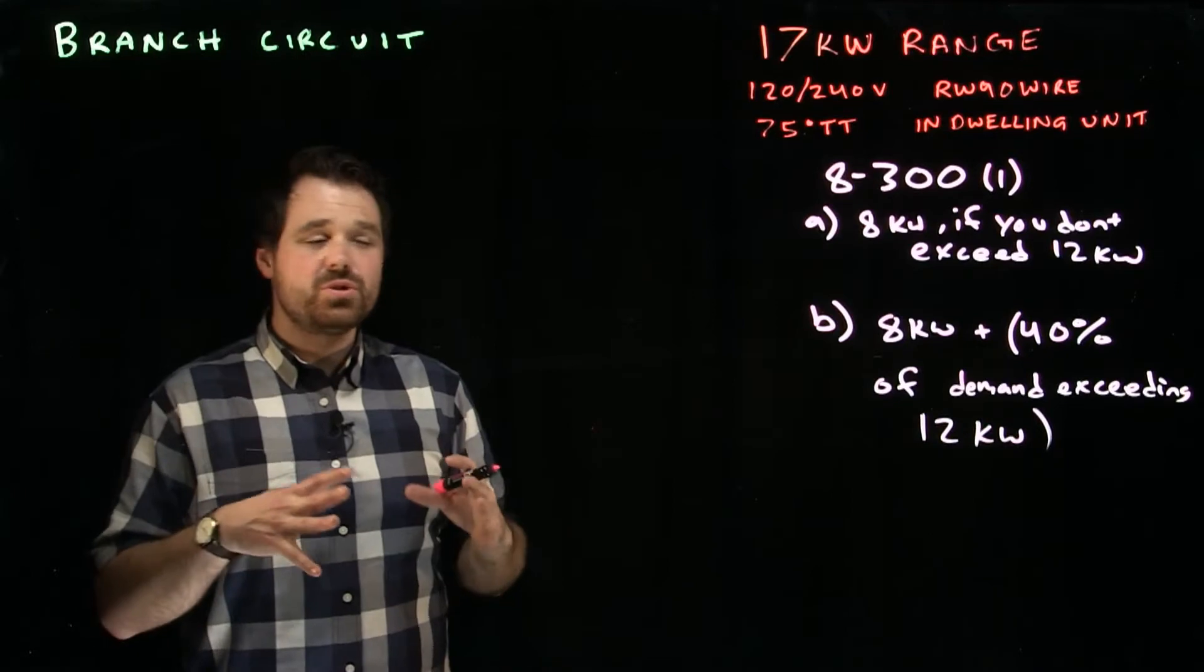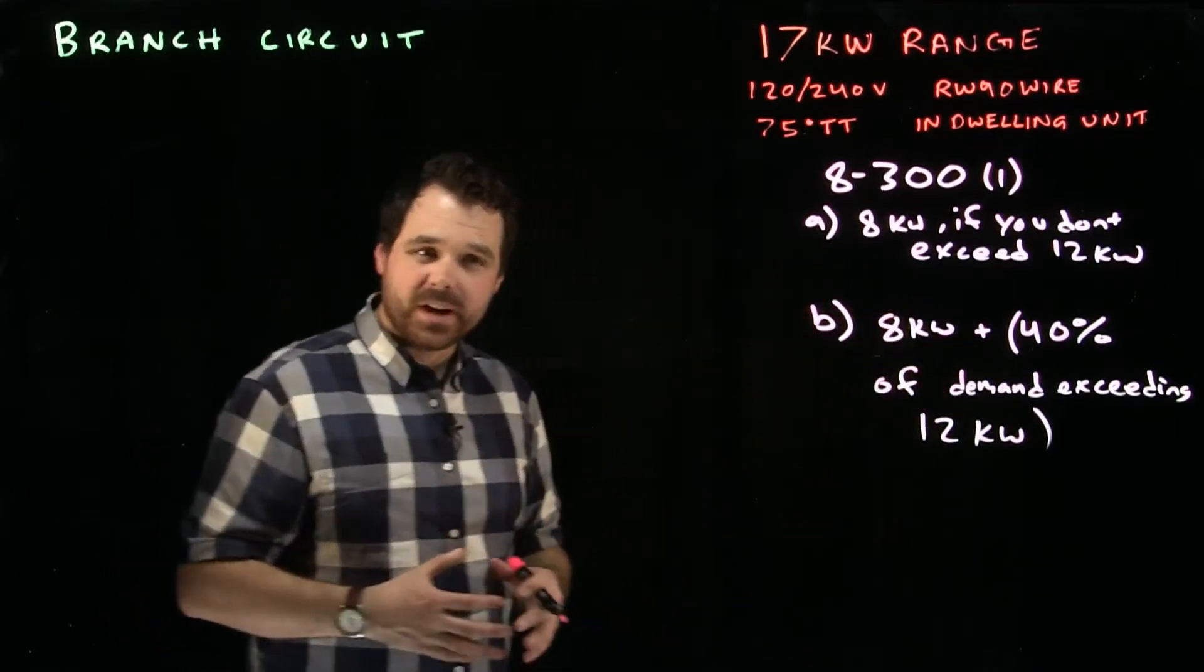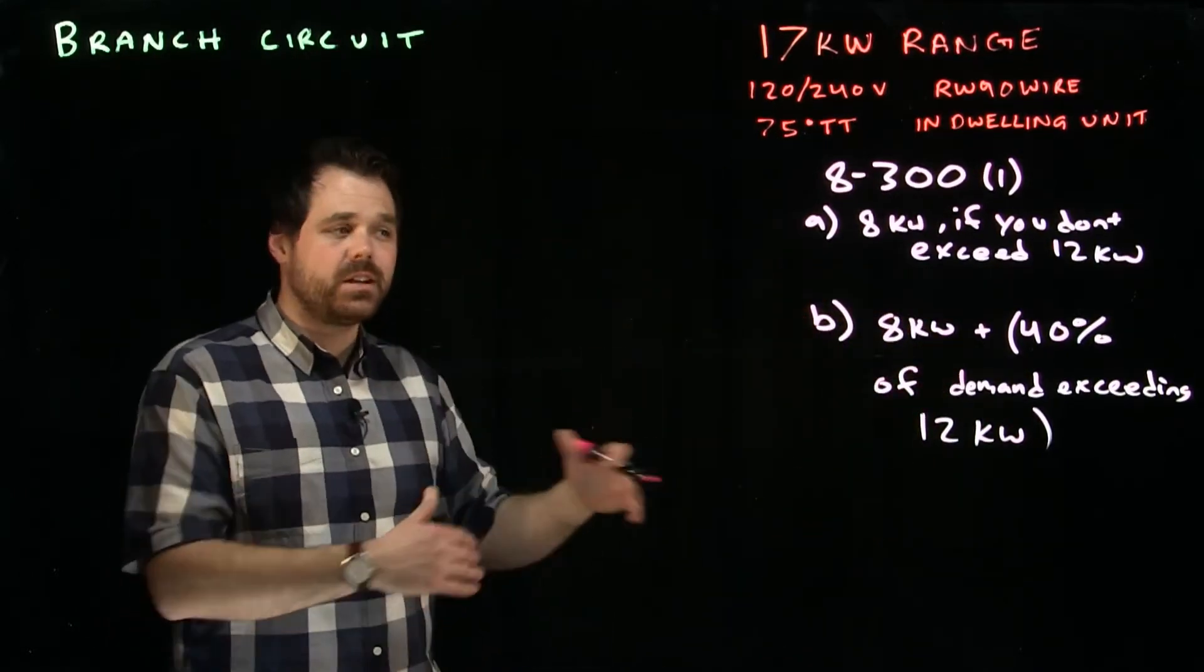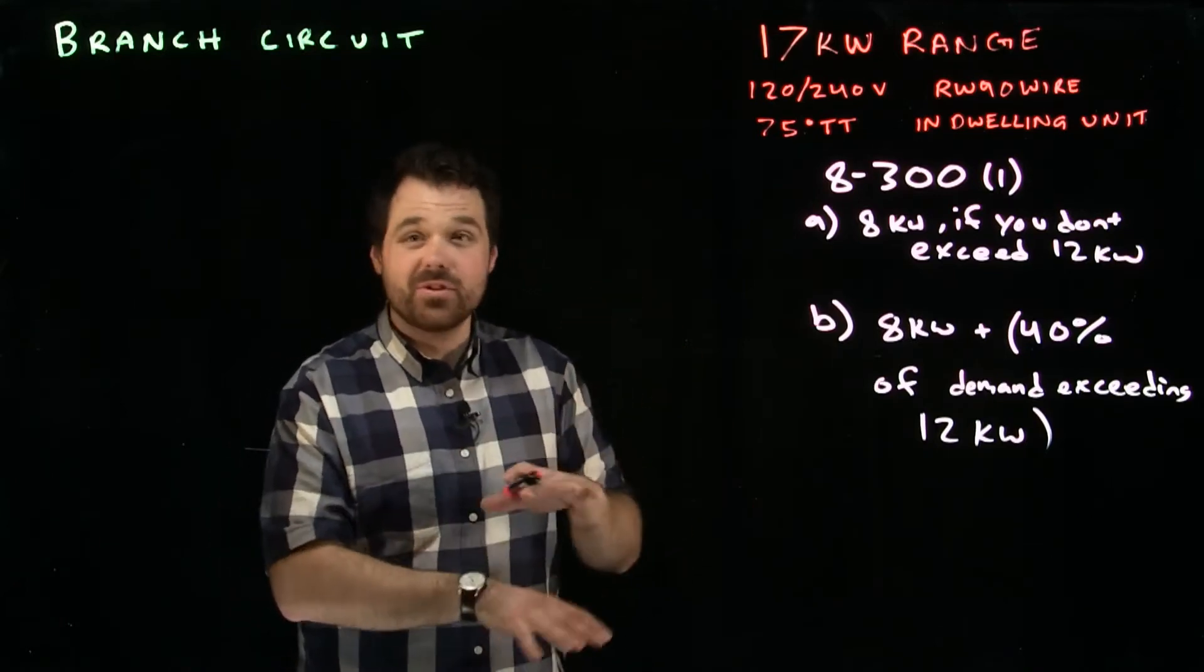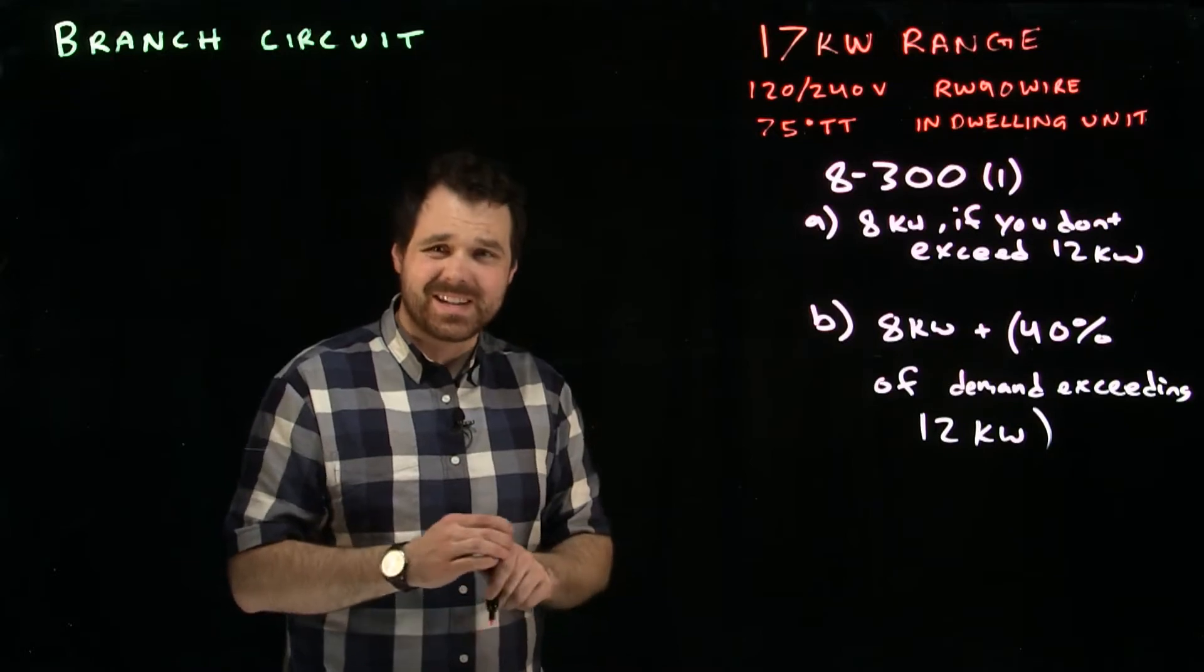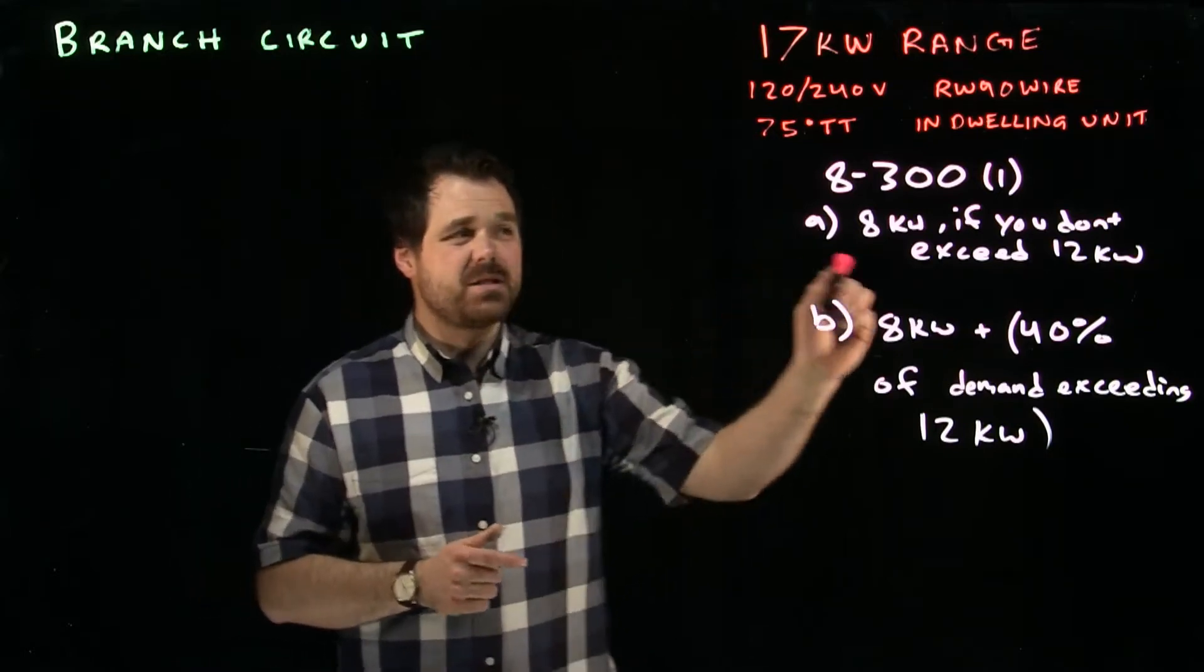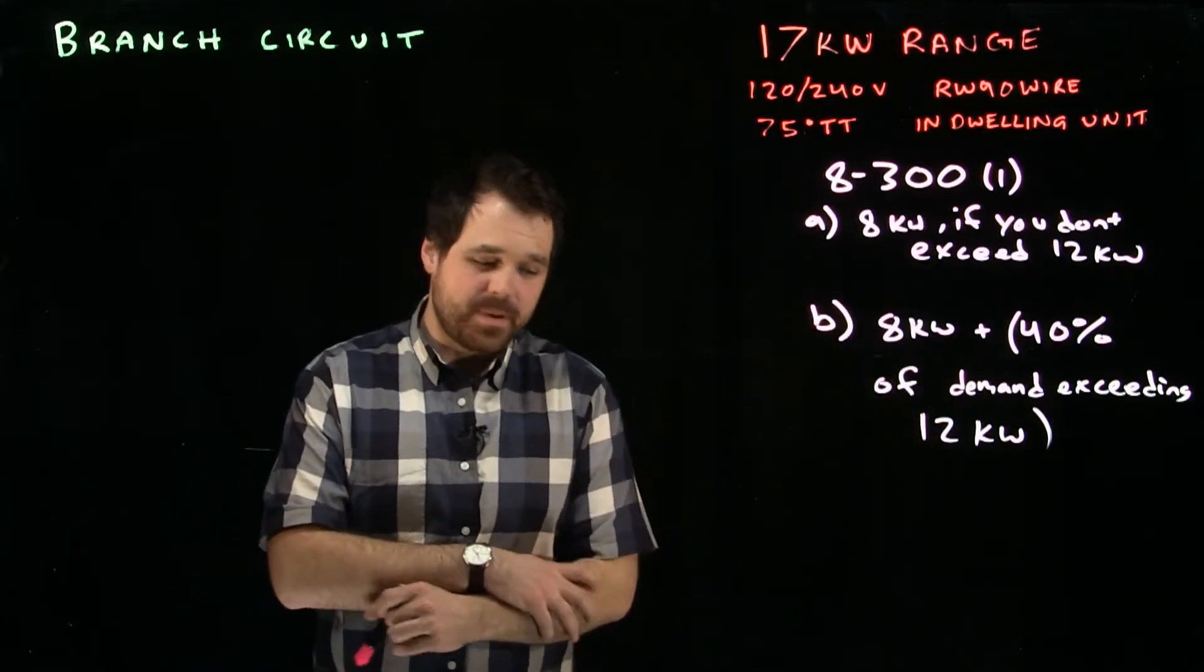So the code book allows us to apply demand factors to a range because with a range, they're rated in what they would use if everything was on. But with ranges, we know that not all four burners and everything inside the range is all going to be on at the same time. So we get to apply a demand factor and size our wire based off of that.